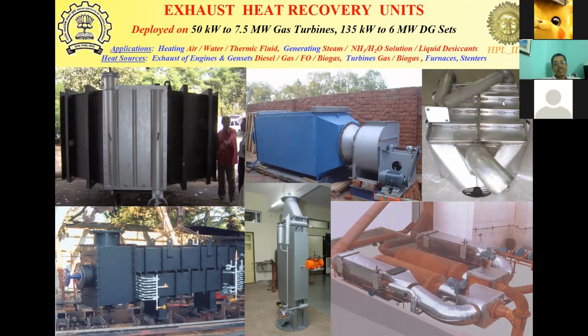Now, where do you get the heat to regenerate that liquid desiccant? The heat can come from various sources. If you have gensets, gas turbine power plants, process waste heat and so on, we can pick it up from there and use it for regenerating the liquid desiccant. Now, this slide summarizes some of our technologies which we have deployed for exhaust heat recovery. In this particular one, the actual heat exchanger is only between this and this, the silver color one, and that is for a 7.5 megawatt gas turbine exhaust heat recovery. We'll see some individual slides later if we have time. But this is for gas turbine exhaust heat recovery to heat up thermic fluid from 230 degrees to 250 degrees centigrade.